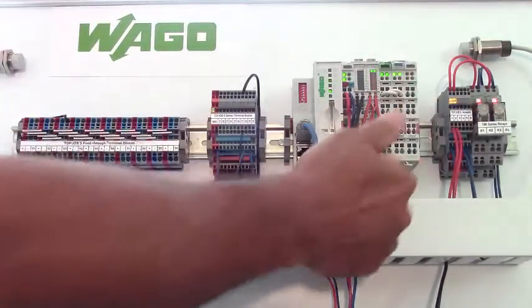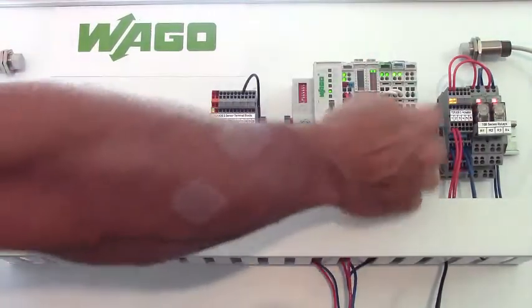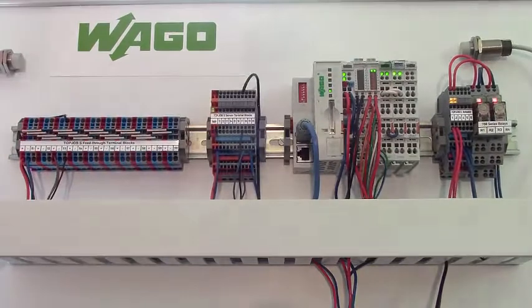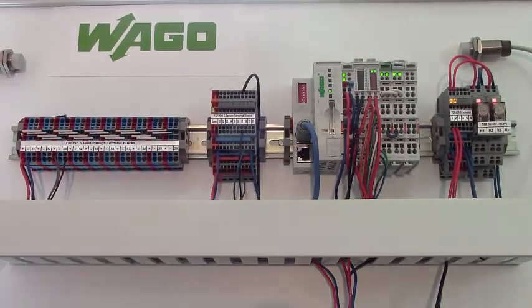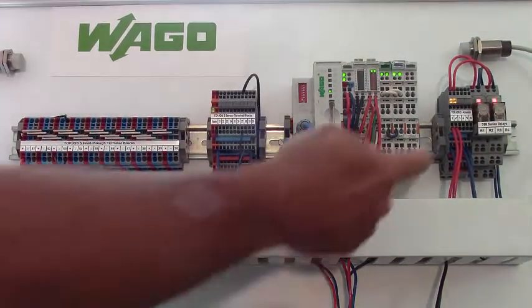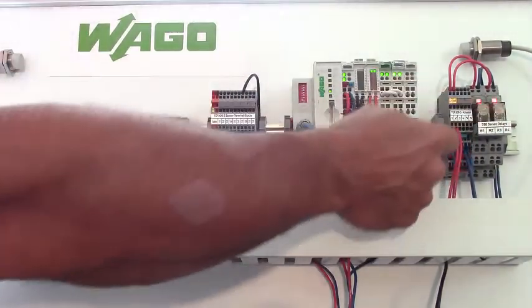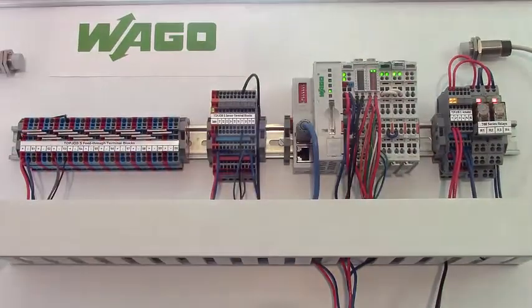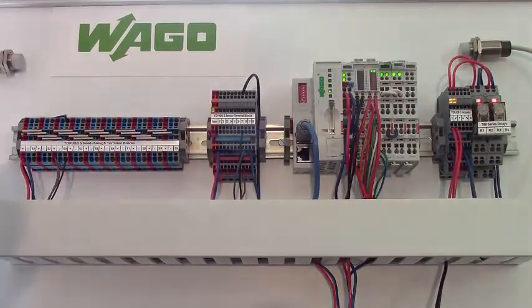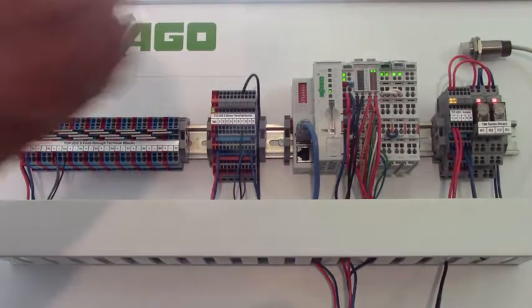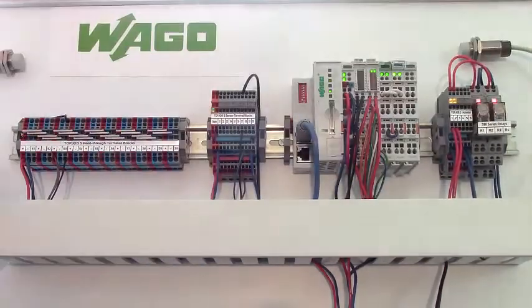If we again split this circuit, we see it's energized here, but for some reason the relay is not energizing or turning on, then we could come down and look at this. Maybe it's a broken wire or a faulty relay, whatever the case may be. But we get a quick visual again by splitting that circuit up.